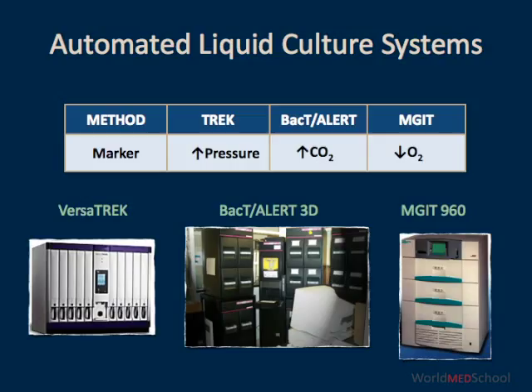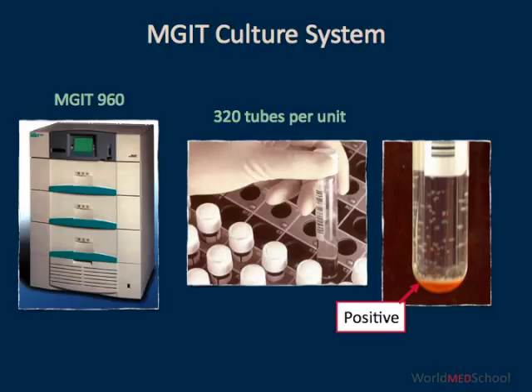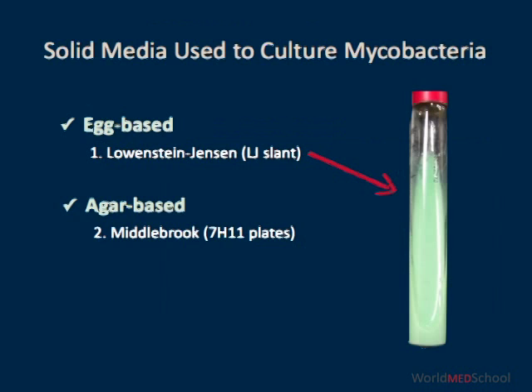This slide shows three different commercial automated liquid culture systems. These systems detect different markers of growth. The TREK system detects change in pressure in the culture headspace. The BacTAlert system detects production of carbon dioxide by bacteria, and the MGIT system detects consumption of oxygen by the bacteria. In the MGIT tubes, also known as mycobacterial growth indicator, as bacteria grow, they consume oxygen, and as oxygen is depleted, a reporter starts to fluoresce at the bottom of the tube and indicates a positive result.